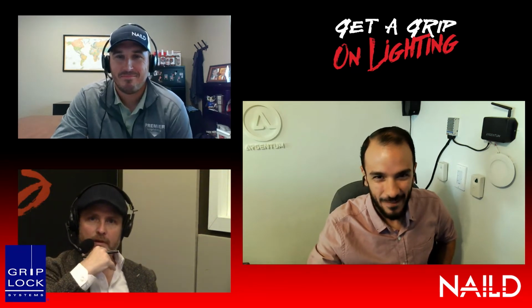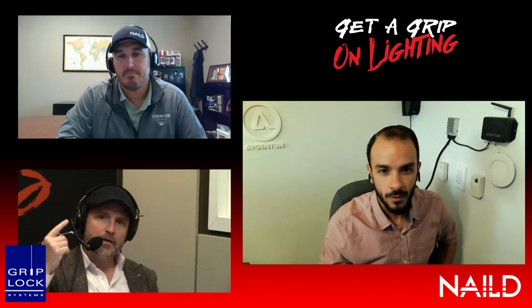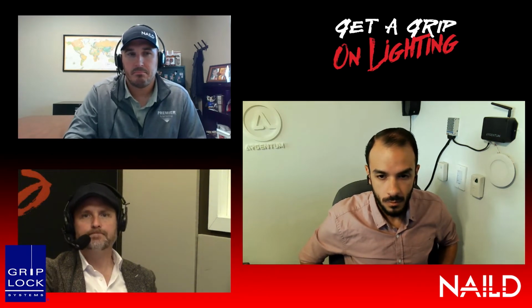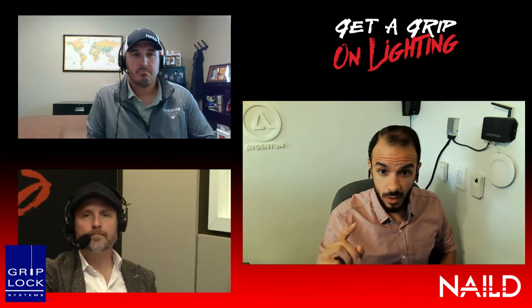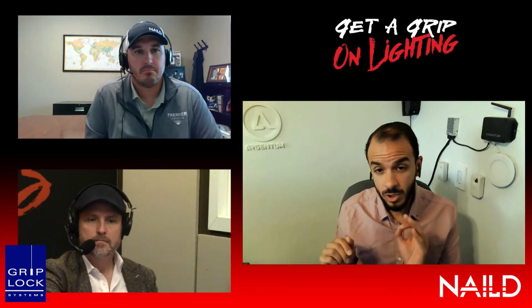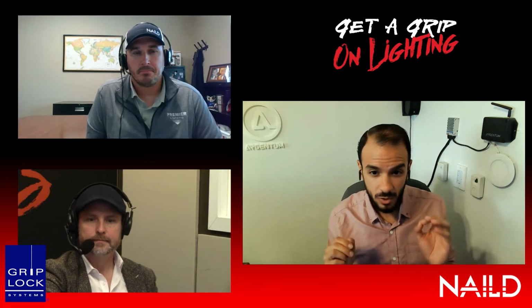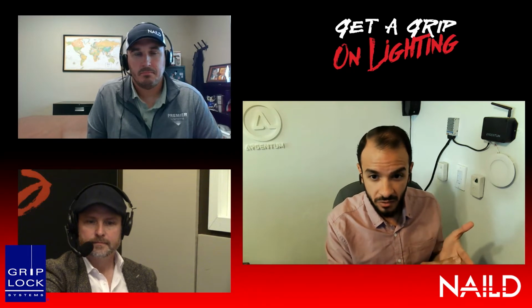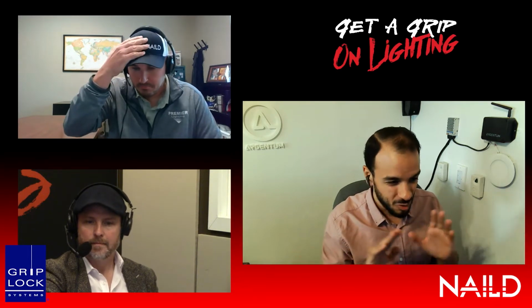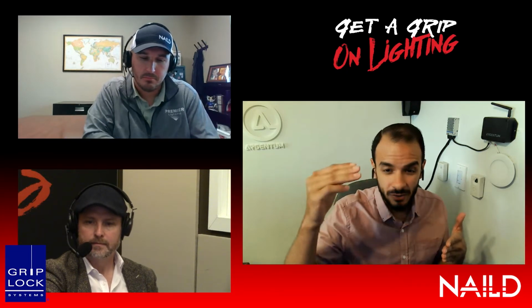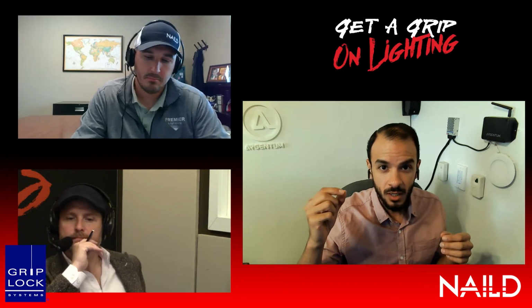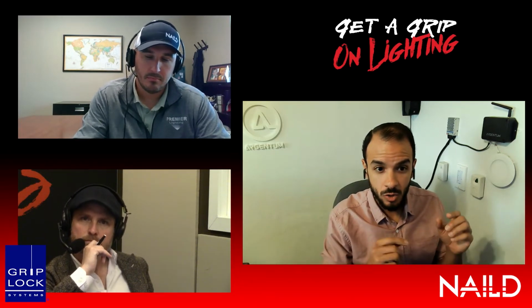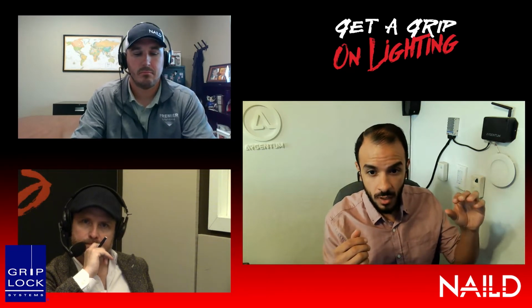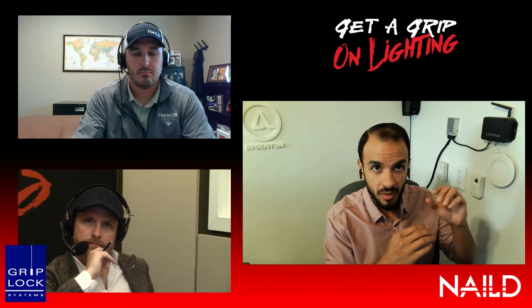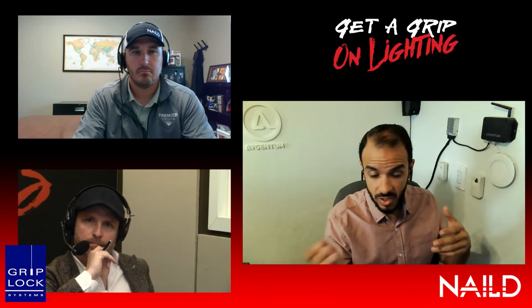Let me ask you a couple questions before we get deeper into the lighting side of it. Number one, can AC wire, so 12/2 BX or 12/3 BX, can it be powered with DC without changing it out? So technically, yes. If the cable is properly marked, which not all are, it'll have a voltage rating for AC and a voltage rating for DC. The majority of cables will have a DC voltage rating that's higher than the AC voltage rating, because the insulation resistance to direct current is a lot higher than it is for alternating current. So the insulator thickness, which is what determines the voltage rating, is a thinner requirement for DC than AC. So most AC cables are safe to carry DC.